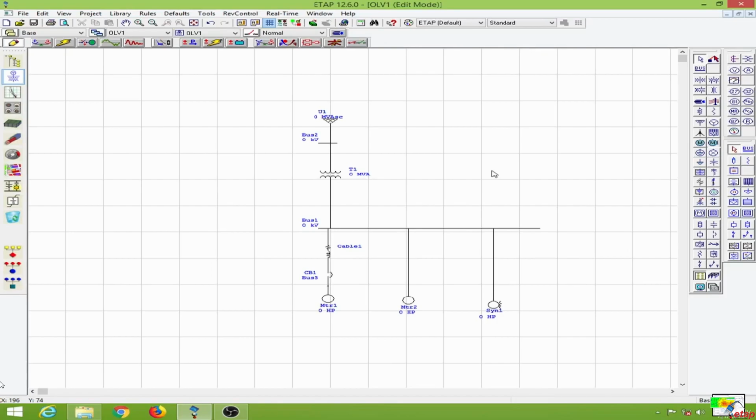And talking about AC motors, there are mainly two types of motors, that is the induction motor and the synchronous motor. And in the induction motor, depending upon the construction, there is the squirrel cage motor and the wound rotor motor. And in case of AC induction motors, we see that it works as a rotating transformer. Due to the short-circuited secondary, there will be a large inrush current in AC induction motors. However, this current reduces depending upon the slip value. When the slip starts to reduce, the short-circuited condition slowly starts to diminish and becomes settled over time.